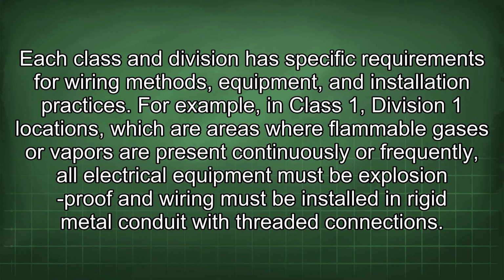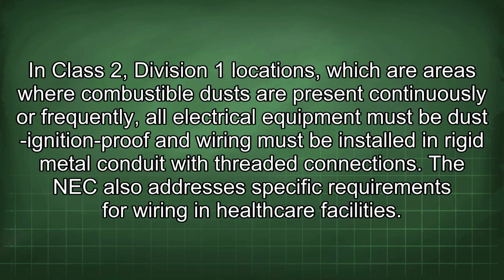For example, in Class 1, Division 1 locations, which are areas where flammable gases or vapors are present continuously or frequently, all electrical equipment must be explosion-proof and wiring must be installed in rigid metal conduit with threaded connections. In Class 2, Division 1 locations, which are areas where combustible dusts are present continuously or frequently, all electrical equipment must be dust ignition-proof and wiring must be installed in rigid metal conduit with threaded connections.